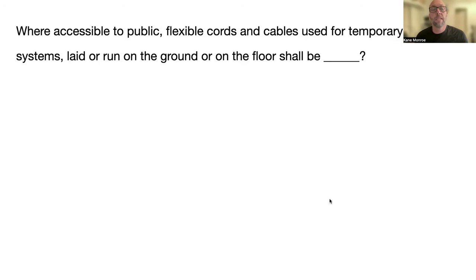Where accessible to public, flexible cords and cables used for temporary audio systems laid or run on the ground or on the floor shall be covered with approved non-conductive mat, 640.45. So back there in 640, I believe we're doing sound systems.